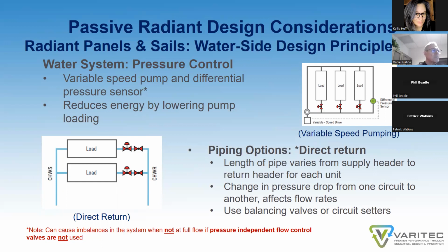There are various piping options. There's a direct return option. Length of pipe varies from the supply header to the return header for each unit. There's a change in pressure drop from one circuit to another, affecting flows. And you need to use a balancing valve and a circuit setter appropriately to the zone load in order to make sure that water is adequately distributed throughout the array of devices that are being used.